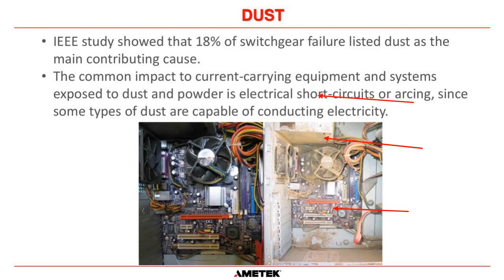And the North Sea, I'm guessing you've never been there before, but it's extremely wet. It rains a lot. It gets foggy. It's very humid, and it's not a nice area. And what had happened was that air intake duct was pulling in not only dust from the room, but moisture from outside. And what happened was, after a certain amount of time, the dust built up on the board. That dust got moist and eventually caused short circuit arcing and completely blew the main control board for that UPS and caused the UPS to shut down, drop the load, and caused the DCS system to lose all of its screens, and the whole platform had to shut down because of it.